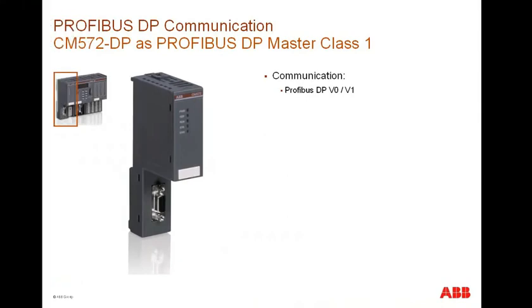The CM572 DP master that we discuss in this example supports both DPV0 and DPV1 communication type. This means it could support both cyclic and acyclic data transfer between the master and slaves. Up to 32 stations or nodes, including one master and 31 slaves, could be operated in one Profibus segment. Segment-to-segment connection is possible with the help of Profibus repeaters. In this way, one could go up to 125 slaves.